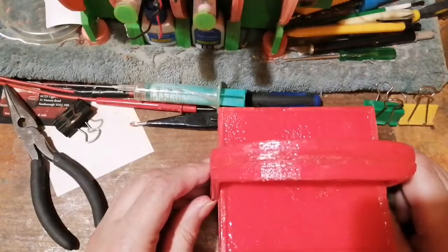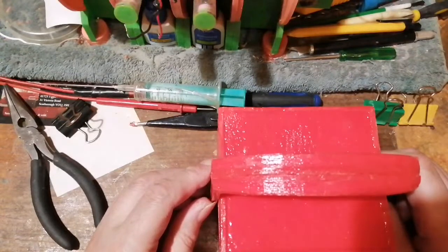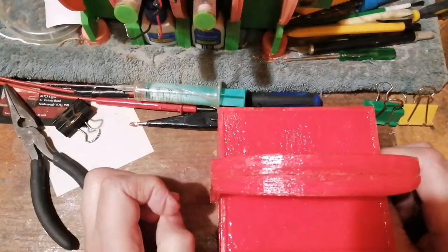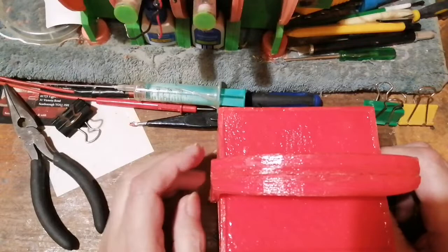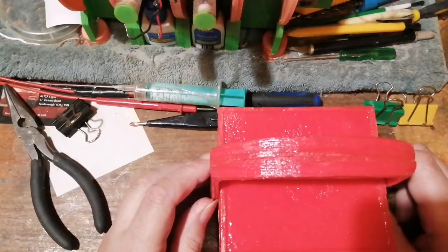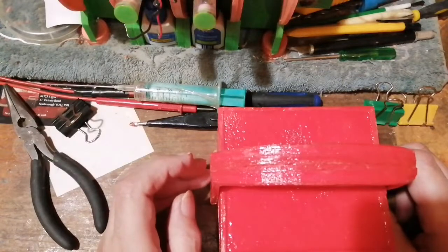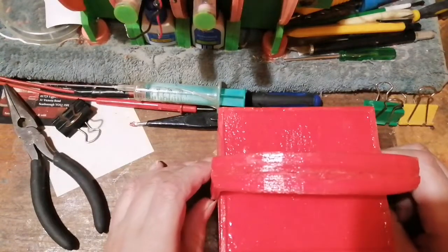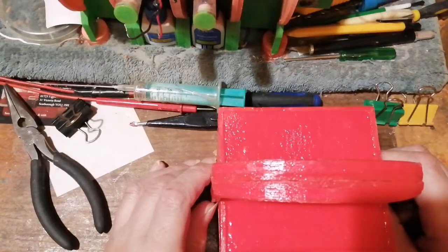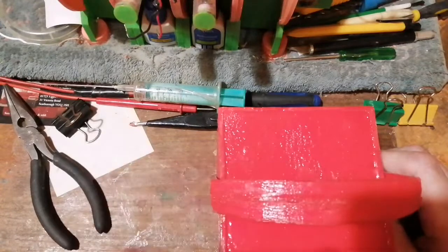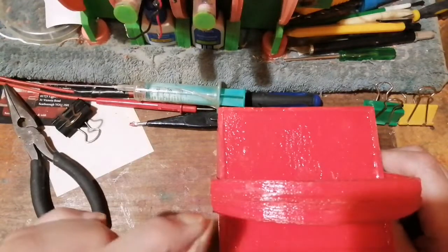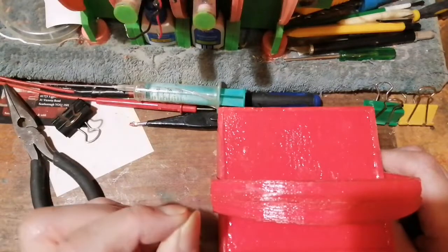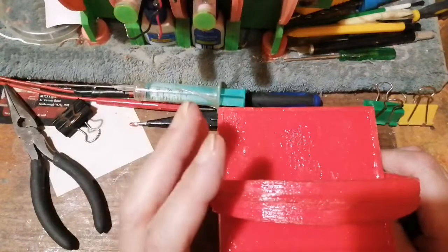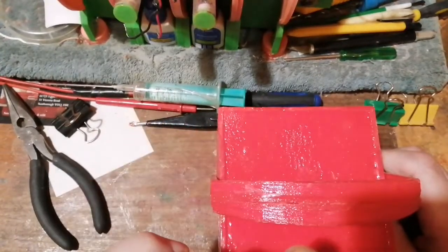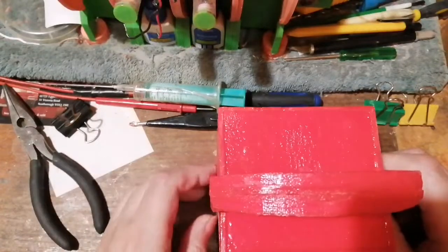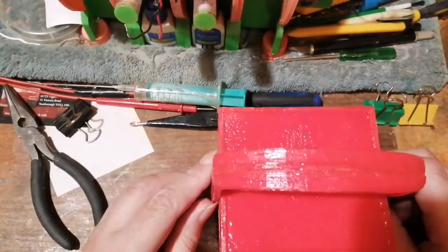A transient suppressor is normally open circuit - it doesn't conduct anything until it detects a voltage in excess of what it's rated for. So say you've got one rated at 240 or 250 volts - if it detects a transient spike above, say, 280 volts, it would immediately conduct and short that spike out. But it wouldn't continue conducting, otherwise it would blow up from the full power coming out of the generator. All it does is snub out the transient spikes in the supply, and they're quite good actually.